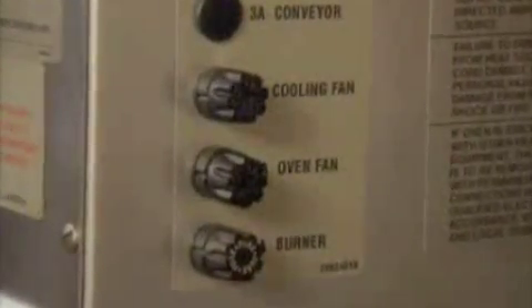Next, check your main circuit breakers and fuses. If the conveyor stopped when the oven was hot, it could be overheating. Check and clean the ventilation louvers and cooling fan covers if needed. It could also be a mechanical malfunction.